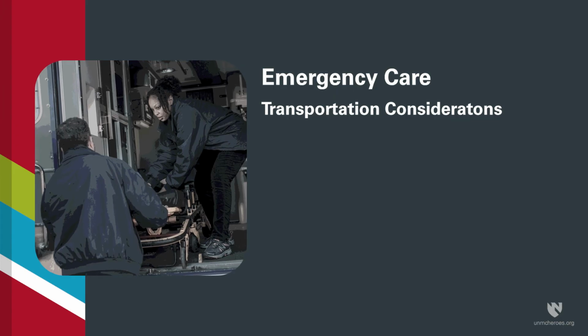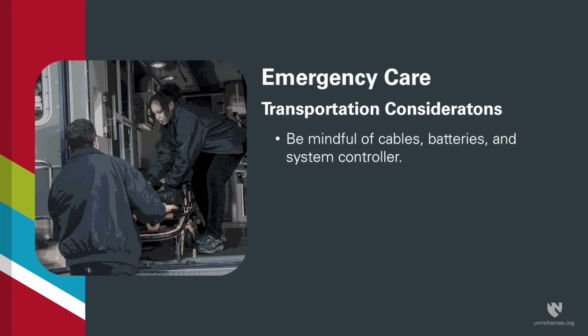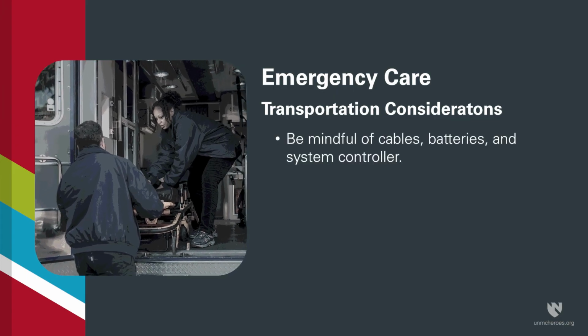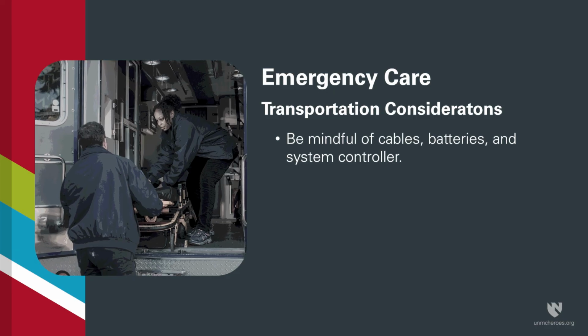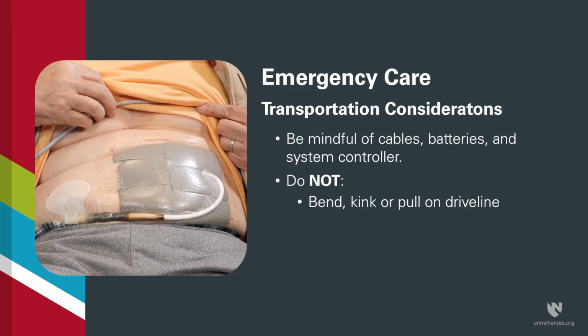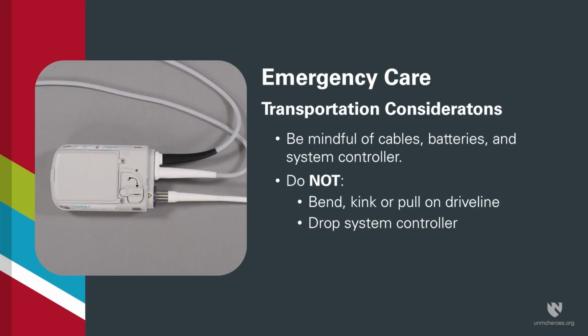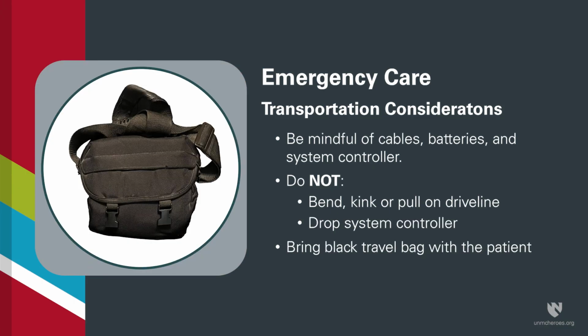When transporting the patient to the hospital, it is important to be mindful of the system controller, cables, and batteries. Ensure you are not bending, kinking, or pulling on the driveline, and be careful to not drop the system controller. You should also ensure the patient's black travel bag accompanies them to the hospital.